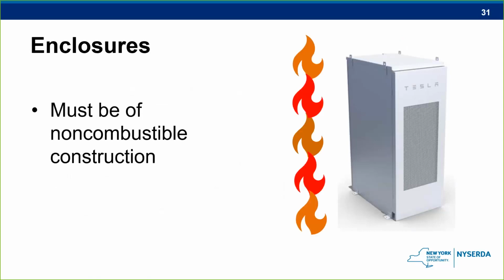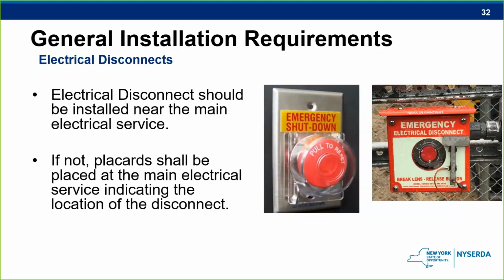This one might seem a little obvious to most of you, but all energy storage systems should be made of non-combustible material. This is to contain the fire within the enclosure so the heat doesn't transfer to other, perhaps nearby enclosures. Electrical disconnects are also extremely important to first responders, and they should be in a secure location with signage to direct the first responders to the proper place. One important point to remember is that even though you may shut down the energy storage system, the stored energy inside the batteries does not necessarily dissipate. It's their job to hold on to it.